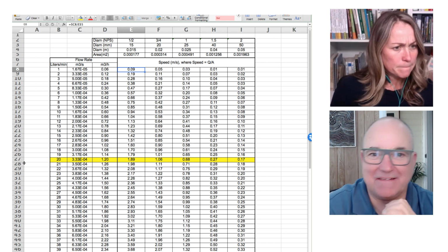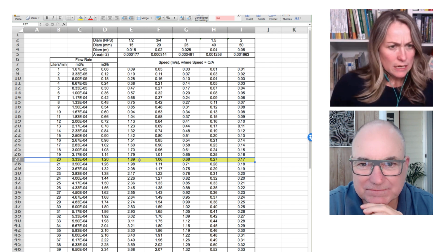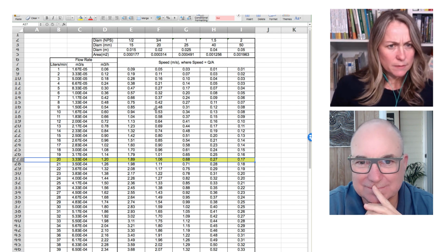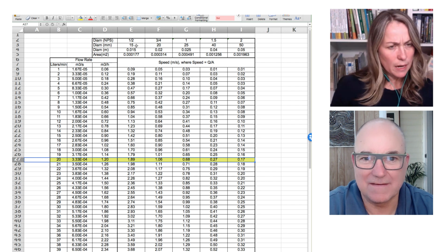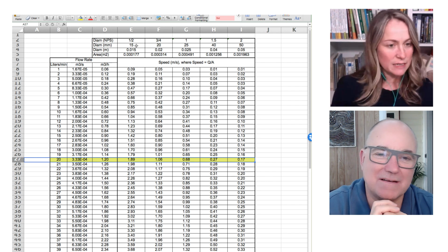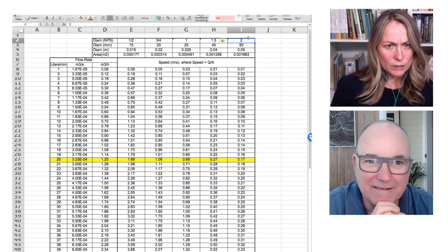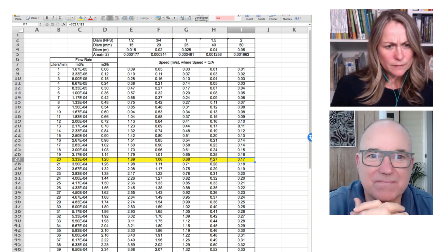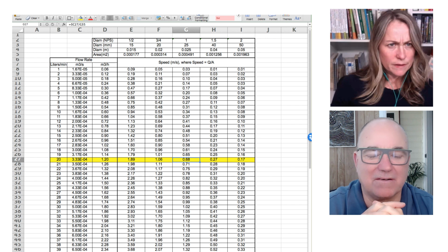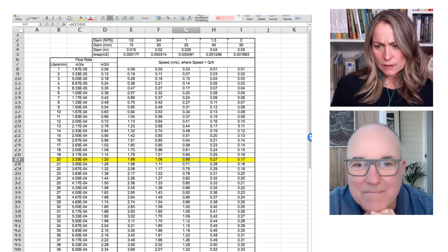So 1.89. Right here, we've got 20 liters per minute, and 1.89 meters per second would be with a pipe diameter of half an inch or 15 mils coming out of the pump, correct? Because we're looking at the speed of the water. So we should make that pipe diameter a little bigger. Would it be 50 mils, 2 inches? It might be 1 inch. You think it'd be this one? Yeah. 0.68? Yeah, for a classic system. So let's try 0.68. Okay, let's try that.